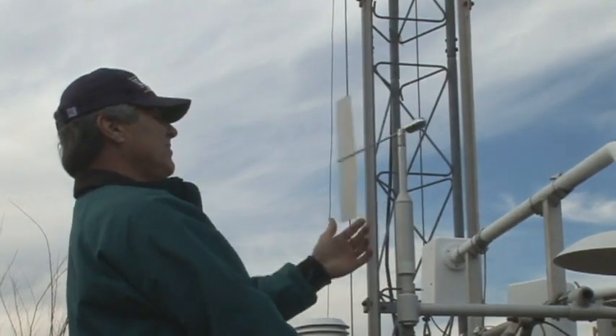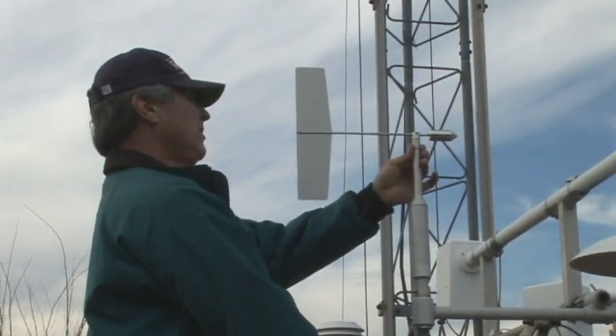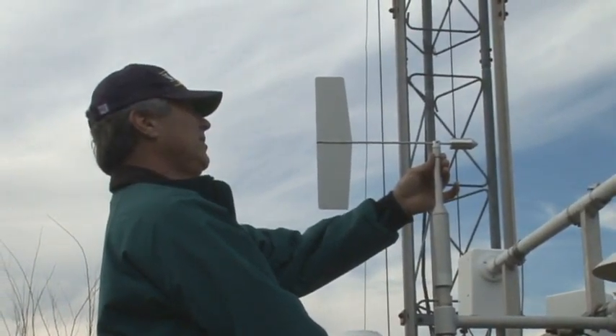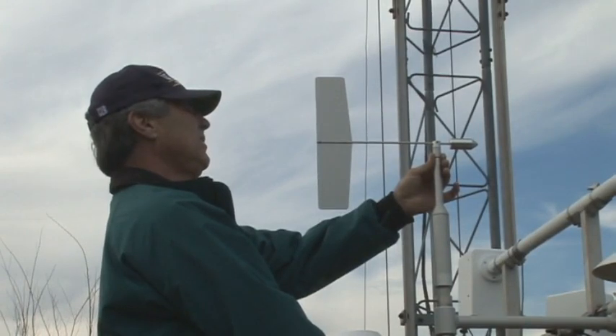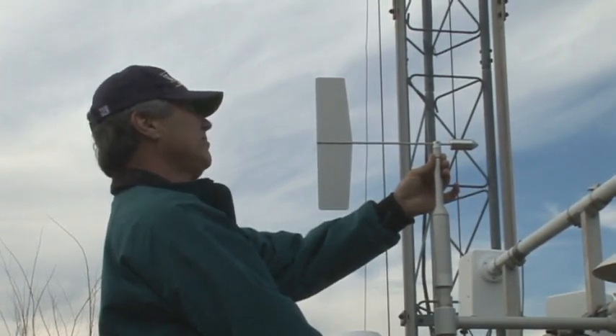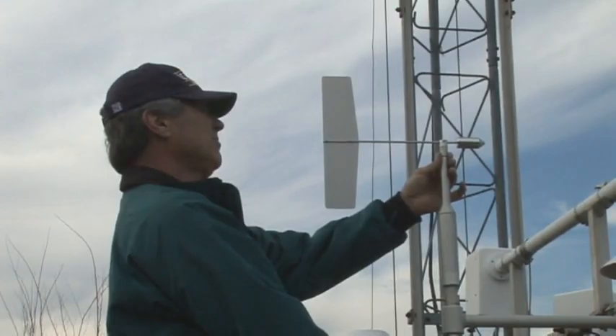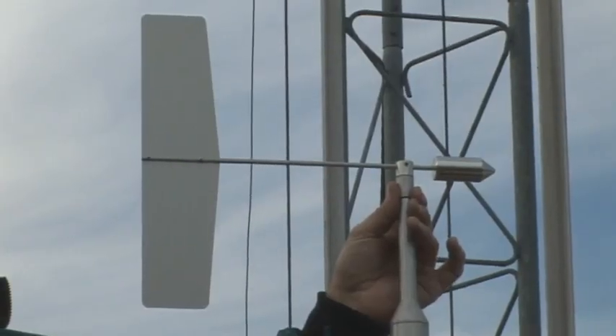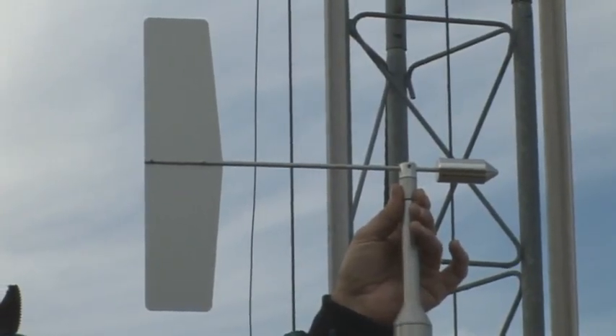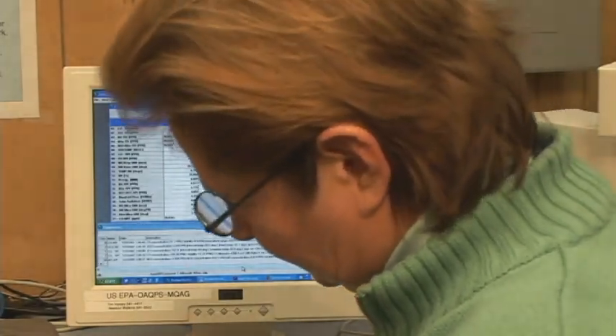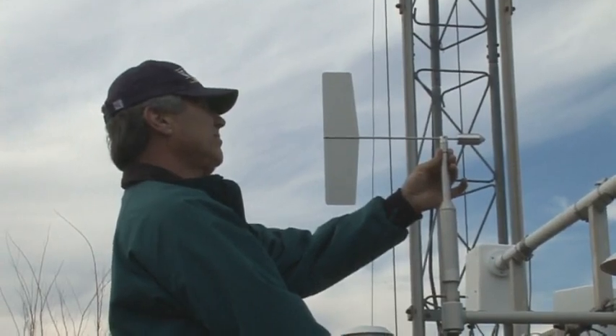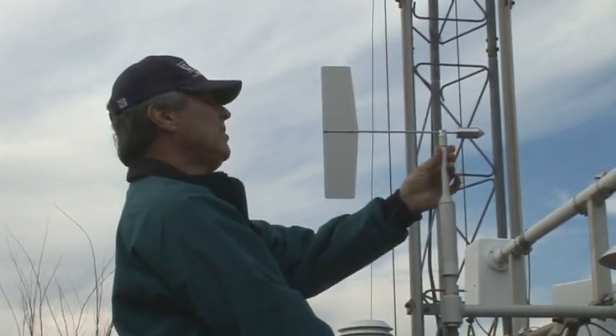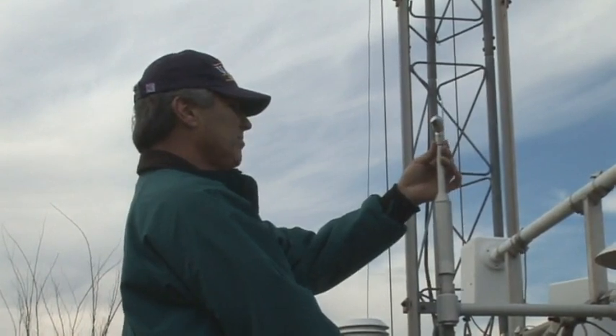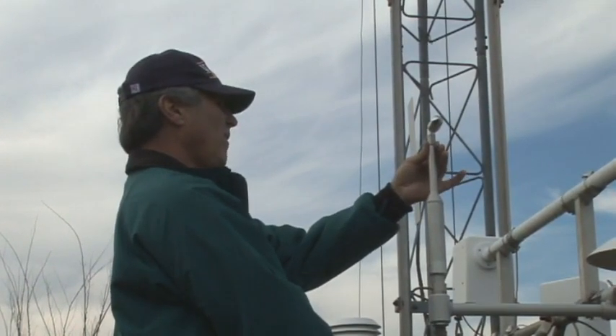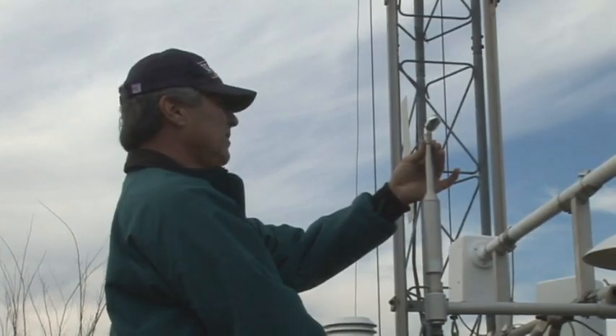With the wind direction vane in place, have the outside technician hold the vane so that it is in line with the instrument boom. Start the test so that the weight or the head of the vane is pointing towards the instrument boom. Have the technician hold the vane as steady as possible. Once the vane is steady, have the inside technician record the response of the DAS. Once the inside technician reads the value from the DAS, have the technician move the sensor 90 degrees in a clockwise direction so that the vane is now perpendicular to the instrument boom. Use a square. This will help.